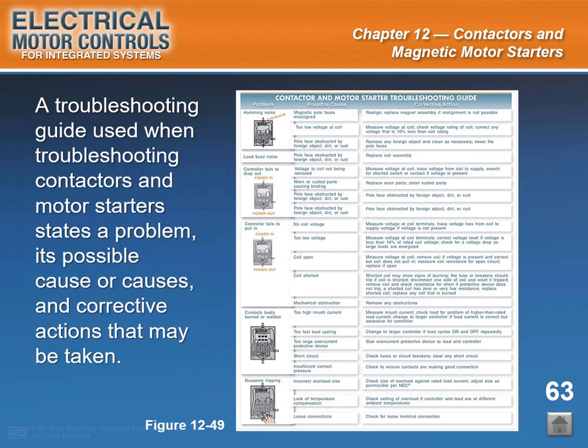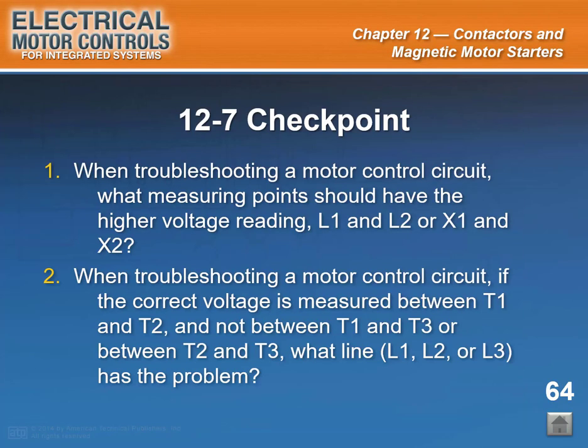Slide caption: A troubleshooting guide used when troubleshooting contactors and motor starters states a problem, its possible cause or causes, and corrective actions that may be taken. See Figure 12-49. Manufacturers know best when it comes to troubleshooting their equipment. They will give you the best advice in the form of a troubleshooting guide. It will allow you to select from a list what type of trouble you are having and then suggest a cause or causes, along with corrective actions you should take to resolve the issue you are having. End of slide 63. Start of slide 64.